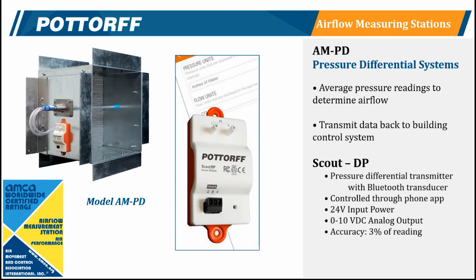One other great thing we were able to launch last year is a much lower cost airflow measuring station that didn't have a damper. So we were able to use the Scout differential pressure transducer with some extruded tubes that we source locally to offer a standalone airflow measurement system.